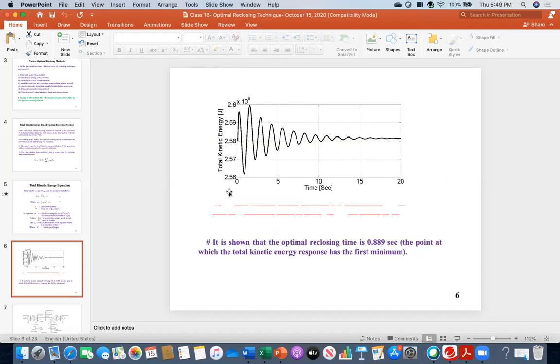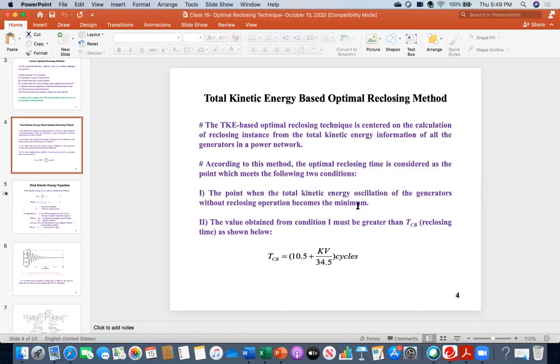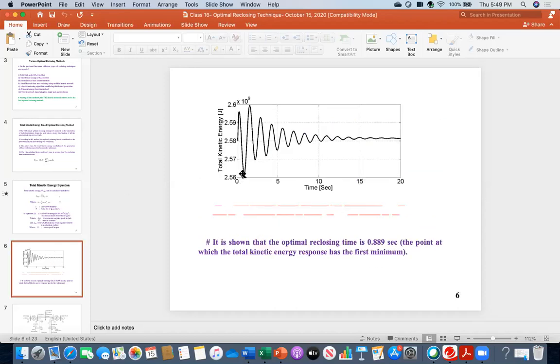So the algorithm will first look at this minimum point and at the corresponding value here. Although it is shown on a big scale, like 0 to 5, 5 to 10, it is definitely some value. I think I have written that point is 0.889 second. The optimal reclosing time is the point at which total kinetic energy has the first minimum. This is the first minimum point. Now the question is, this statement does not say whether it is the first minimum point, or the second or third one. It just says the point when it becomes the minimum. So the algorithm will look at the first minimum point.